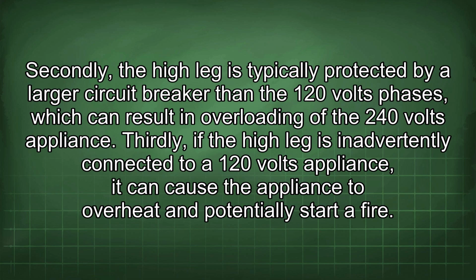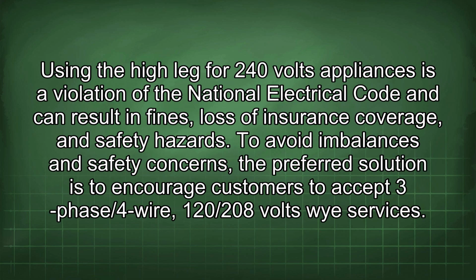Secondly, the high leg is typically protected by a larger circuit breaker than the 120 volts phases, which can result in overloading of the 240 volts appliance. Thirdly, if the high leg is inadvertently connected to a 120 volts appliance, it can cause the appliance to overheat and potentially start a fire. Using the high leg for 240 volts appliances is a violation of the National Electrical Code and can result in fines, loss of insurance coverage, and safety hazards.